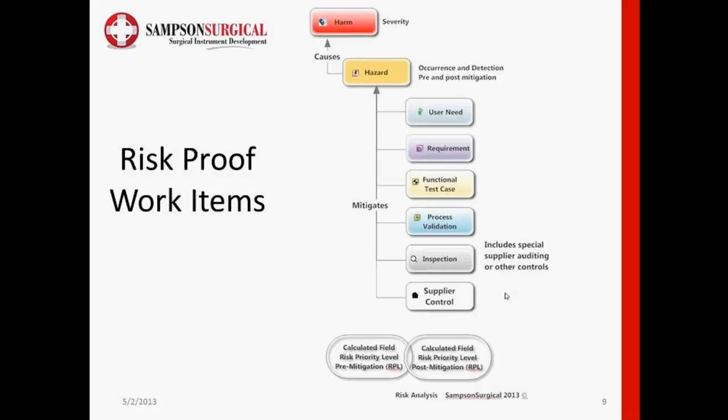And you can see how this would be a very powerful way for us to address an adverse event happening in the field. If something happened, we could go back to our risk analysis, identify the harm, and we'd immediately have a set of hazards. You'd immediately have a set of mitigations to those hazards, and it would all tie out to the testing in your V&V testing that you've done, and/or other testing that you did as just mitigations to the hazard, even if you didn't do it as a result of your design and development effort.